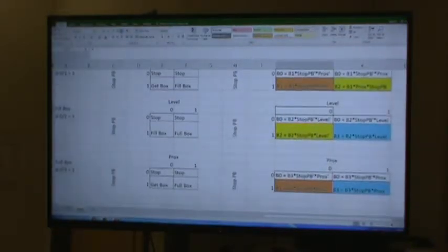So start push button. The next expression is down here. It's B1, stop push button, and not prox. So we need a structure like this. We need B1, we need stop push button, and not prox. Okay, that takes care of that expression. Finally, for the last B1 equation, we need 2 non-inverting and 1 inverting. We need to reference bit 3, the stop push button, and then finally not prox. Okay? And that takes care of programming bit 1.